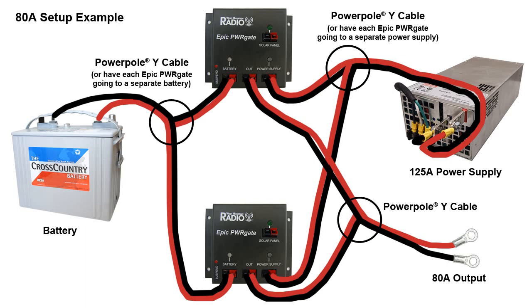One PWRgate can supply up to 40 amps continuously from either a power supply or a battery. Two PWRgates can be connected in parallel to supply up to 80 amps. Shown is one example of an 80 amp setup. It is also possible to have an 80 amp setup with two batteries and/or two power supplies. Each PWRgate can have the maximum charge current set up to 10 amps. The supplied current should be at least 80 amps for the output plus the maximum charge current for each battery. Make sure that you are using Powerpole cables that can handle the current being used.